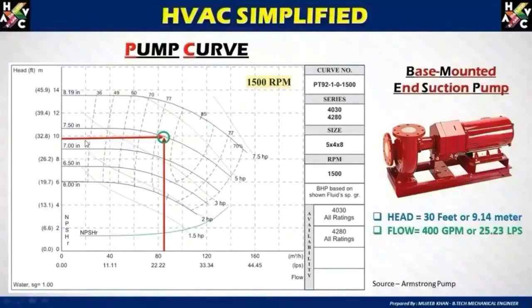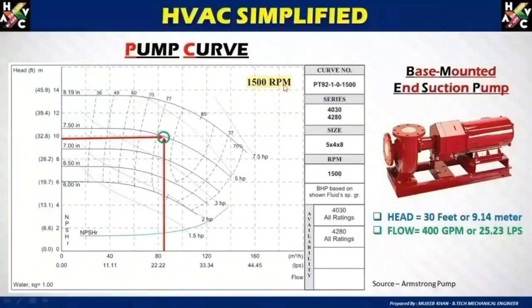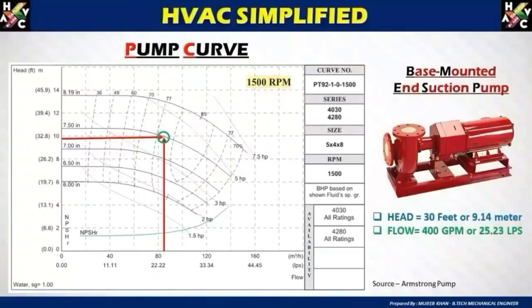At the operating point, the efficiency is more than 70 percent and the impeller size is 7.5 inches. Depending on pump capacity, different impeller sizes can be used. The horsepower shown below is 5 HP, which is consistent with our manual calculation. On the right-hand side you will see the RPM of the pump, and based on this RPM you size a 7.5-inch impeller. The right side also shows capacities and sizes known as the pump series number. This is how you size any chilled water pump based on GPM and head loss.